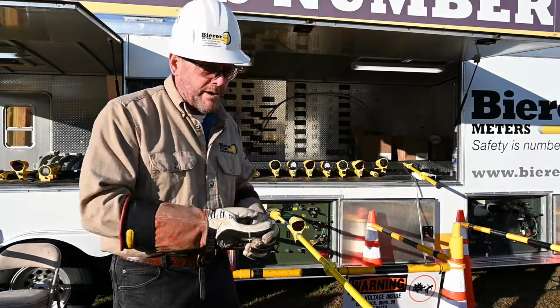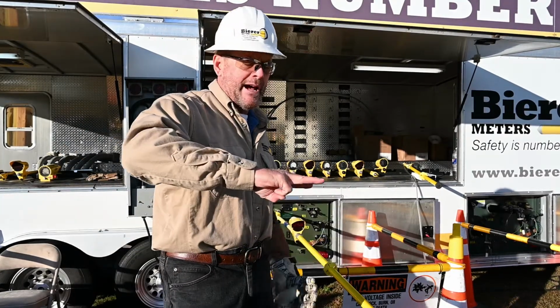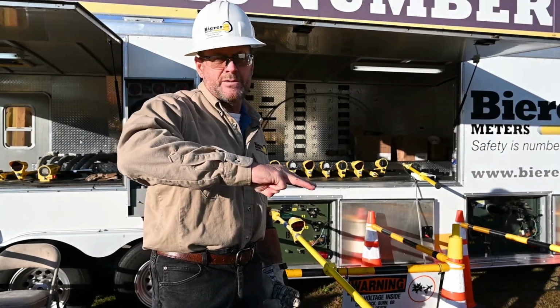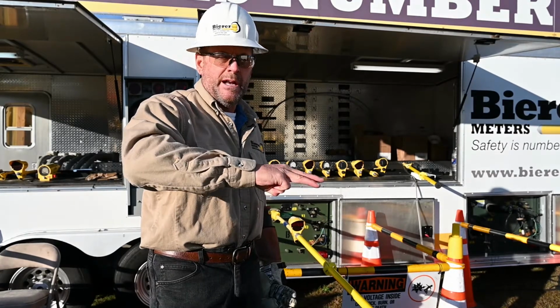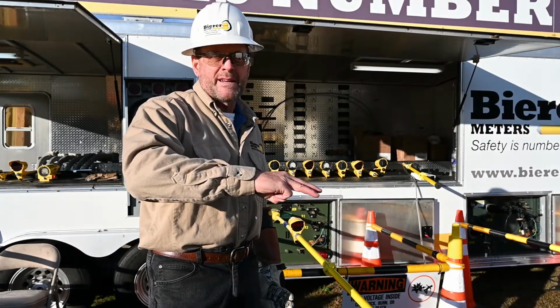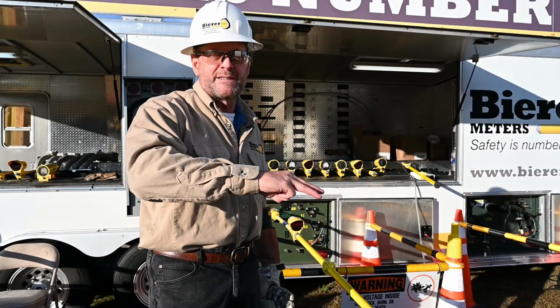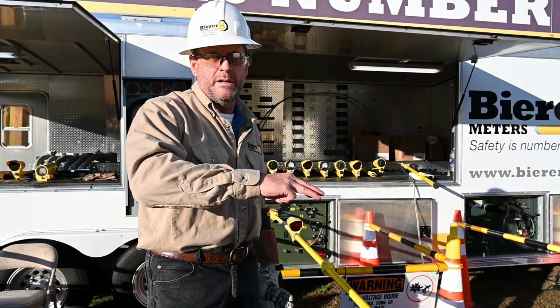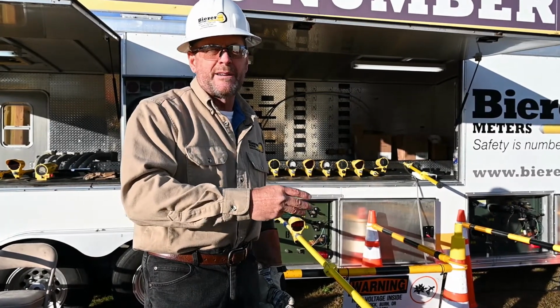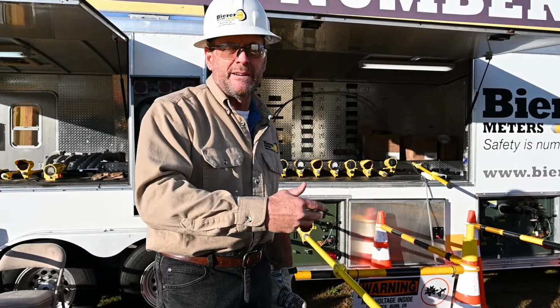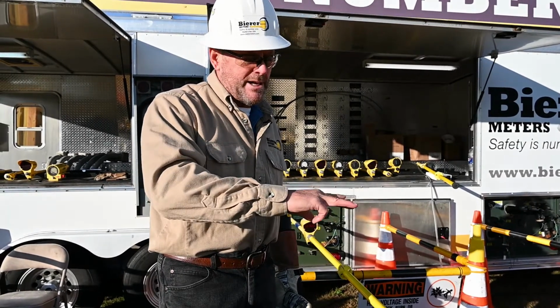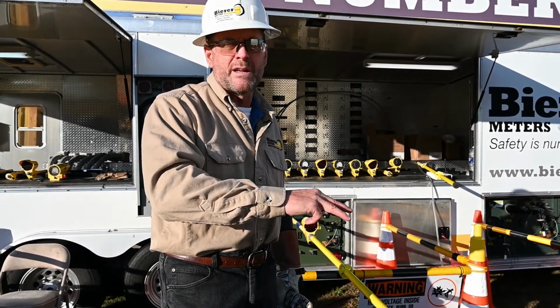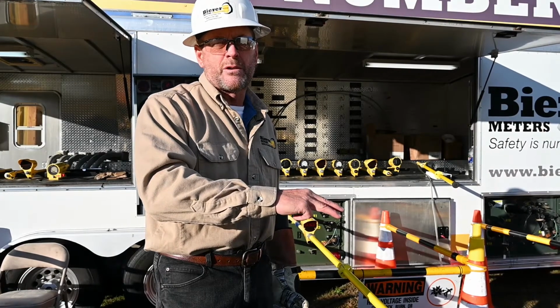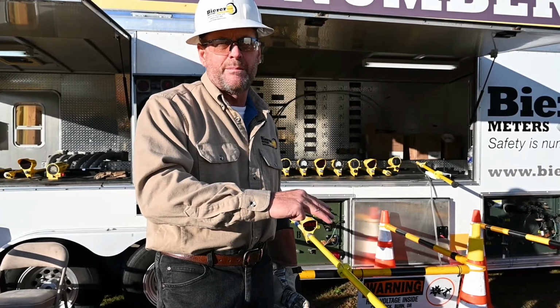If you're phasing and you've got three hot bushings close side by side with each other, and you've got the cabinet nearby, those other phases are going to influence that tool somewhat. Let's say you're wirelessly phasing, looking at voltage. That meter head's going to react with those other phases, and it's going to create skewed numbers, not accurate numbers.